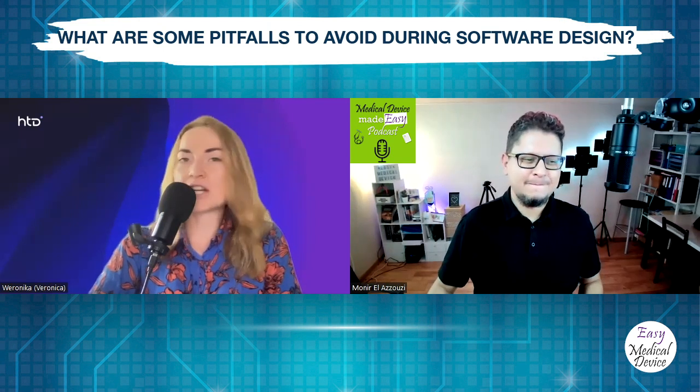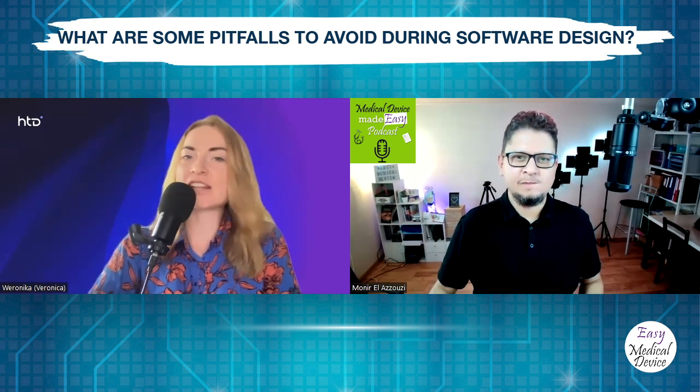Next one, I would say it's very close to my heart. It's agile methodology. It's the expertise to develop software as a medical device. And I call it a lack of knowledge of how to use agile methodology that will be compliant with IEC 62304. And IEC 62304 is the standard that everyone should follow when designing software as a medical device.